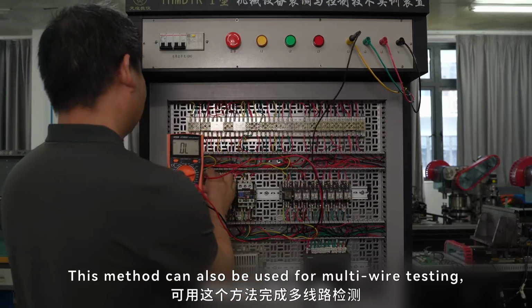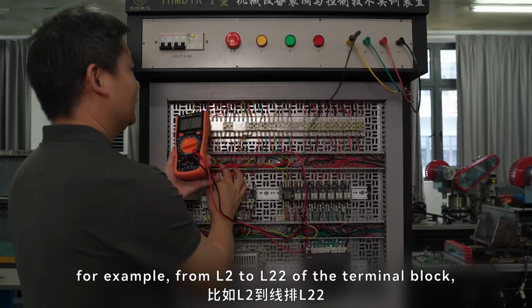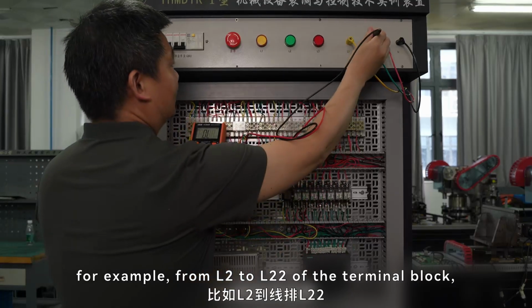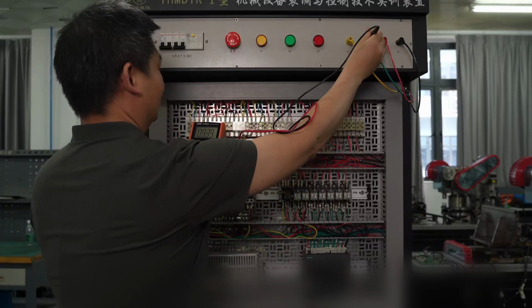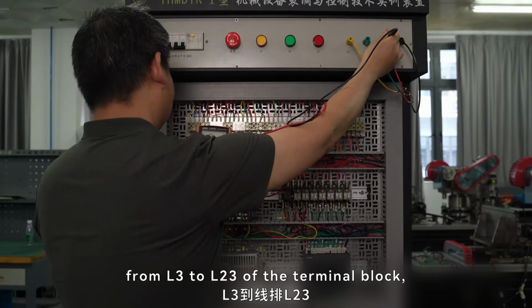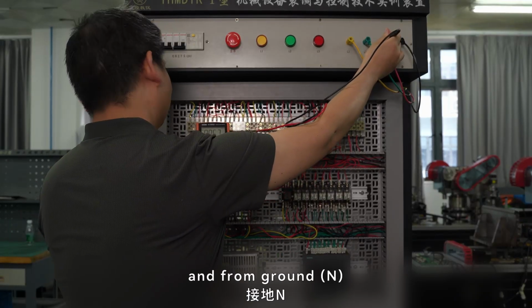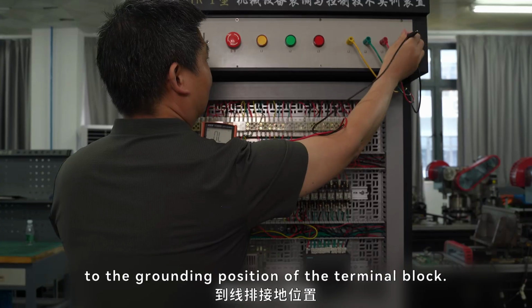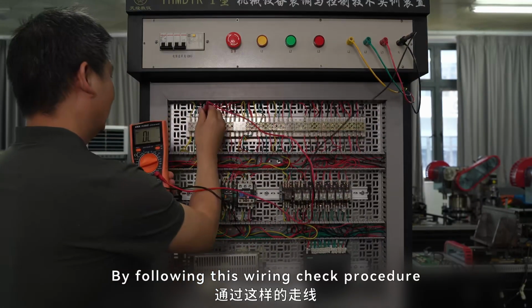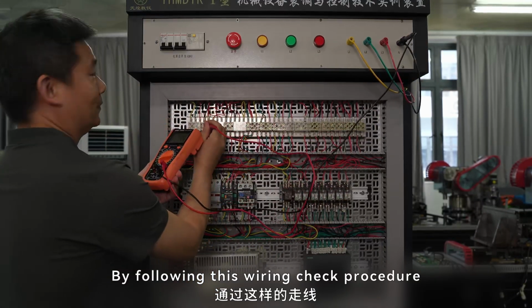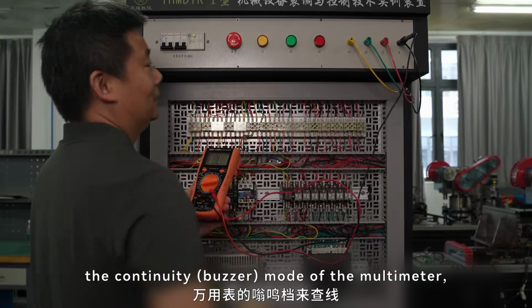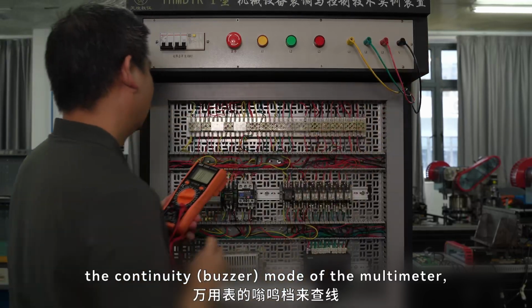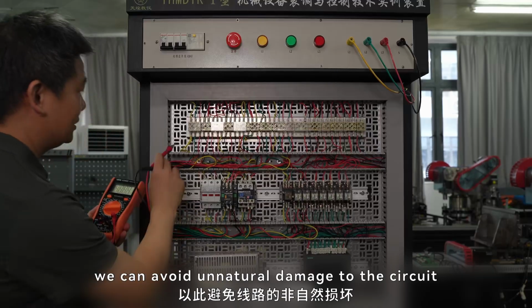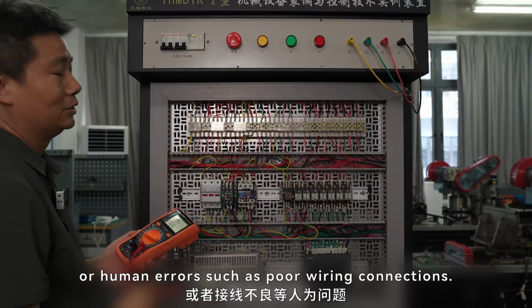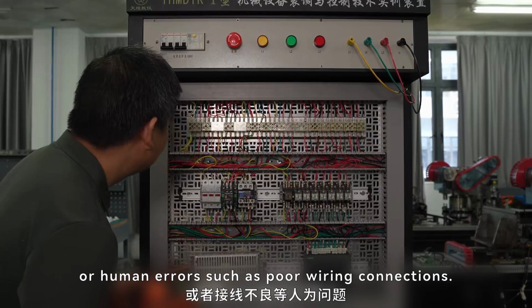This method can also be used for multi-wire testing, for example, from L2 to L22 of the terminal block, from L3 to L23 of the terminal block, and from ground N to the grounding position of the terminal block. By following this wiring check procedure and properly using the continuity buzzer mode of the multimeter, we can avoid unnatural damage to the circuit or human errors such as poor wiring connections.